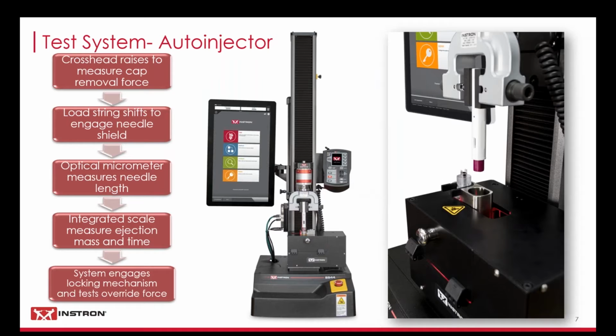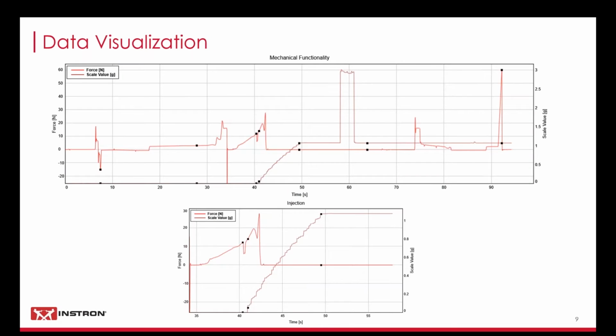Finally, the crosshead moves up, locking out the needle shield, and moves back down to either determine the override force or simply ensure the lockout mechanism is functioning properly. All of the data collection is synchronized and captured in the Bluehill Universal software, providing an unparalleled level of analysis. Customizable graphical outputs provide the user a simple way to visualize the information. Looking at the injection graph, we can superimpose the force and scale data to fully characterize the injection event.